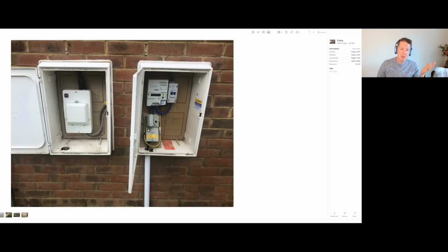If we fitted an MCB in here, it's likely to blow quicker. So if there was an overload on the house for just a few seconds or a few minutes, it could trip the circuit breaker, and that could cause inconvenience to the customer. So I'm weighing all this up and thinking, what can we do here? Could we possibly get a Hager consumer unit that has a carrier for an 80 amp fuse and a 32 amp MCB next to it, and we could fit a surge protection device in there? That's my kind of idea, but let me know your thoughts in the comments, as I said.